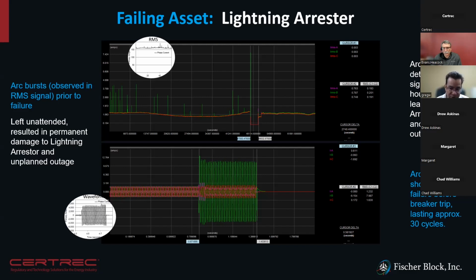And then the zoomed in view of the waveform upon breaker trip is in the bottom there. And interestingly, it took about 30 cycles to clear. So that was an issue where the relay now is being looked at for malfunction. And then those snippets there in white, those little ovals, those are from an IEEE report talking about lightning arrestor failures, and we've included them on the slide to show the similarities in some of the captures our platform has done within WaveIQ.